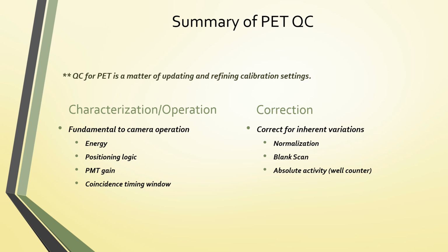When we're looking at the characterization or operation of the system, it's fundamental to the camera's operation. We want to look at the energy, the positioning logic, the PM tube gains. If there is a system that has PM tubes, it may be a newer digital system. In that case, you're still looking at energy resolutions and high voltage supplies and things like that. It's just a little different. And then we also want to look at the coincidence timing window.